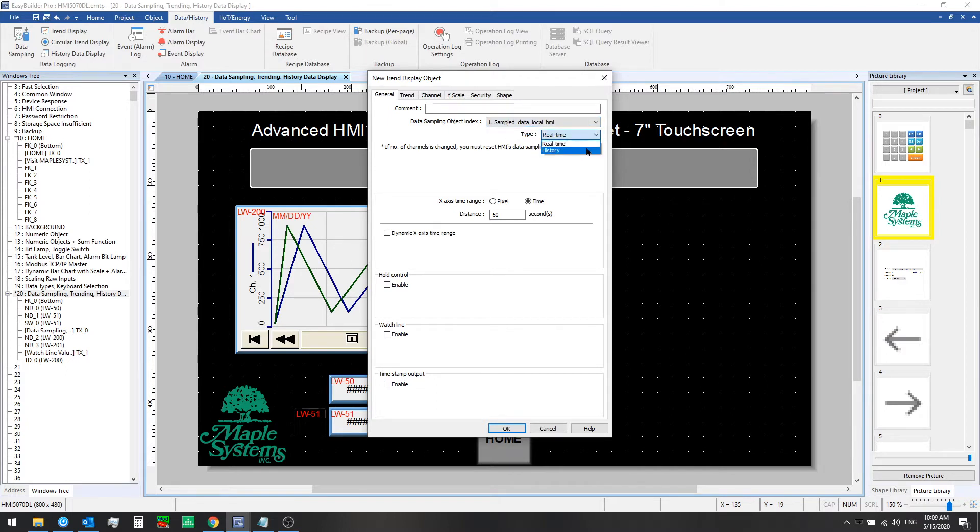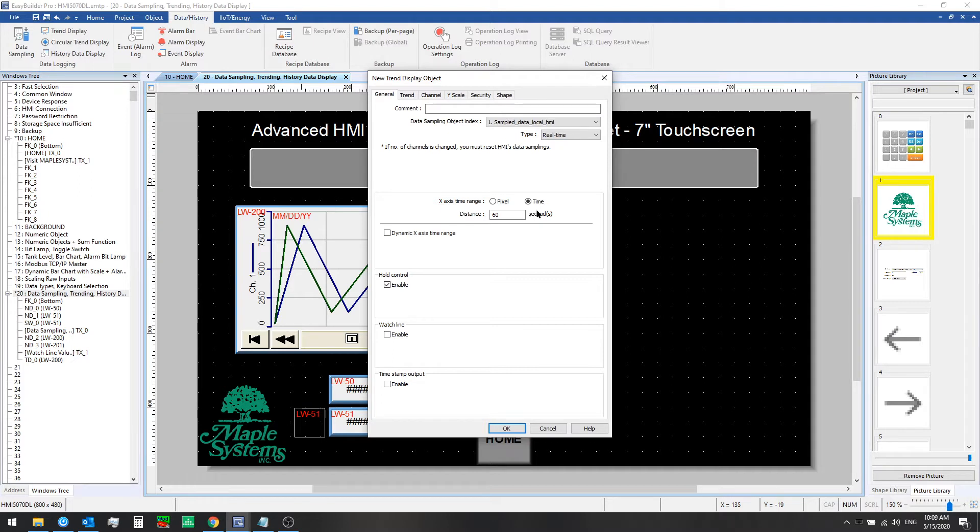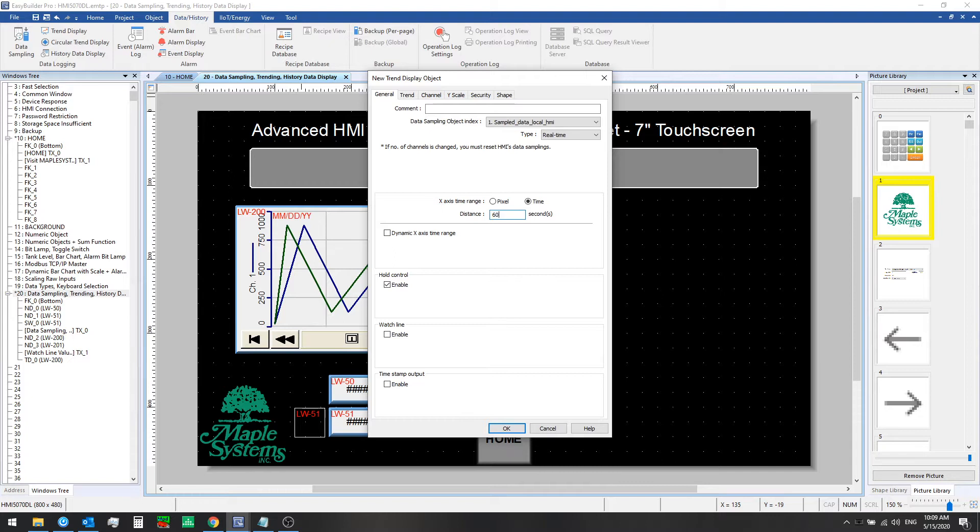Select real-time or history mode. Real-time gets us the latest values right away, and then set the x-axis time range however you wish, either time mode or pixel mode. With pixel mode it spaces out each data point by a number of pixels, or time uses a total number of seconds to put along the x-axis and show that much data at a time on the chart.